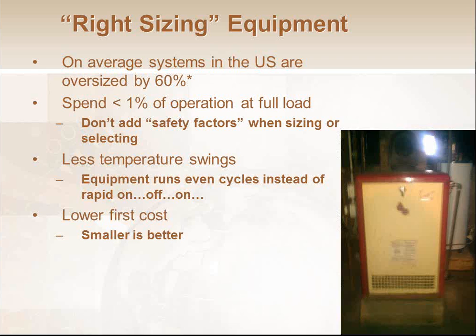You can't go too much smaller. I know it gets into some of the classes we do, but one of the ways we do it is we go around and measure all the radiation in the building. So we literally count all the radiators, their height, width, number of sections, and so forth. If it's a baseboard job, we measure all the fin tube, just the fins, not the whole enclosure, just the fin part. And we go to our tables and say, okay, this radiator or baseboard or radiant floor or air handler or whatever it is can put out this many BTUs maximum.